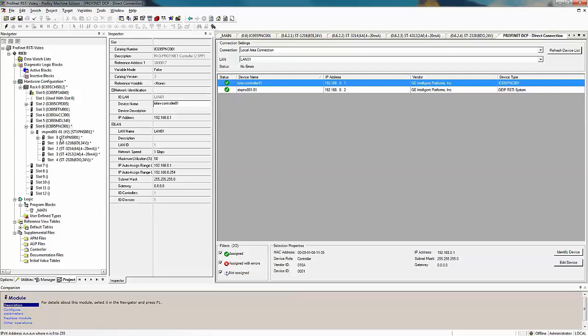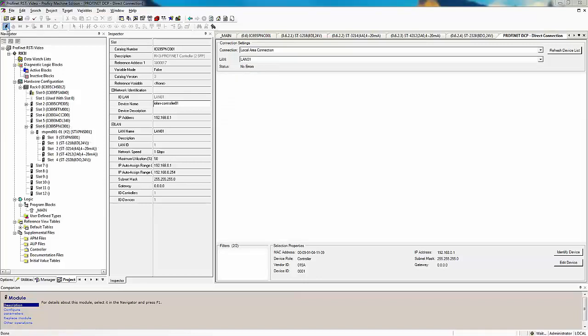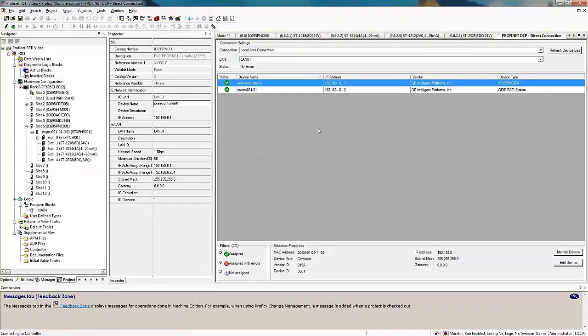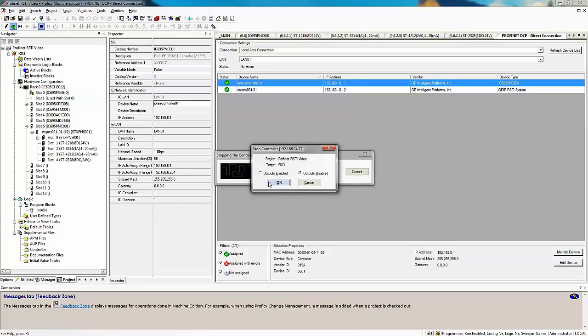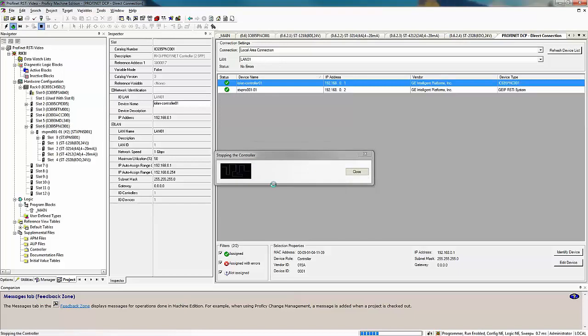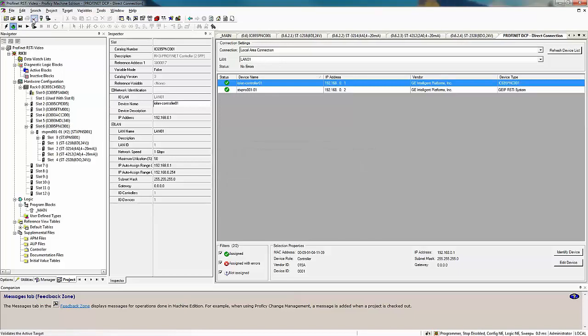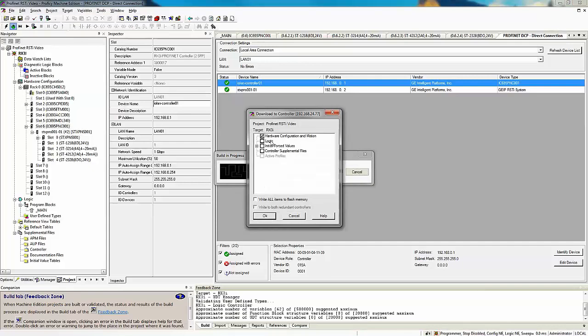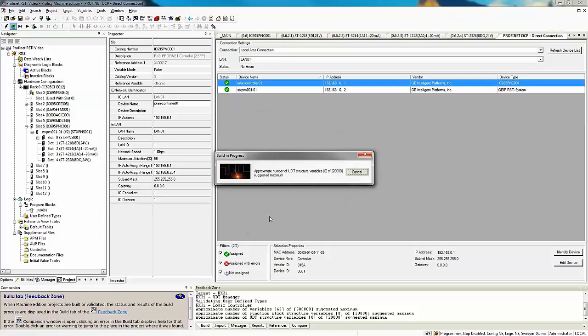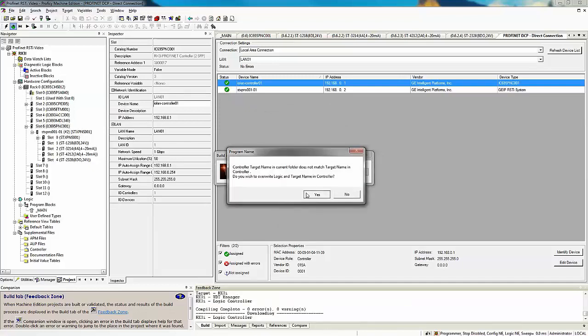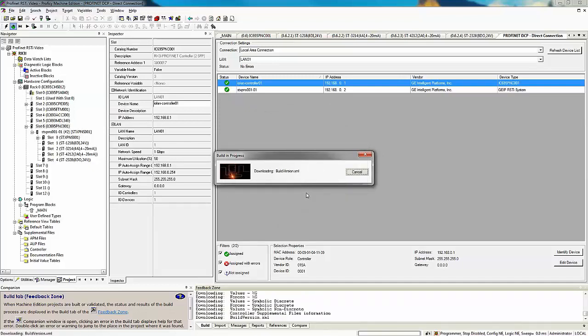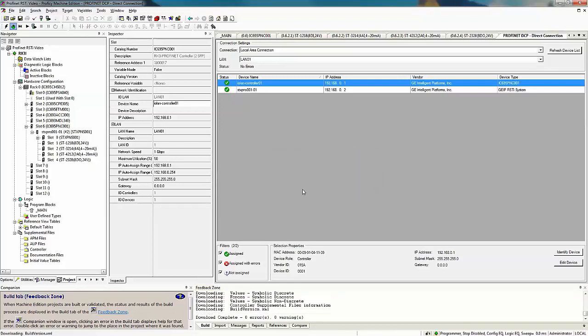Now that we have our PROFINET set up here I'm going to go ahead and click my lightning bolt to go online with my system. I can see down here at the bottom that I'm in monitor mode, run enabled, logic equal, configuration not equal. Let's stop our controller and download to the system. I'll send my hardware configuration, logic, and initial force values. The name doesn't match so we'll say proceed. It builds my system, checks for error, and downloads. Now we can see that we are configuration equal and logic equal down here on the bottom and that we've added our PROFINET LAN.